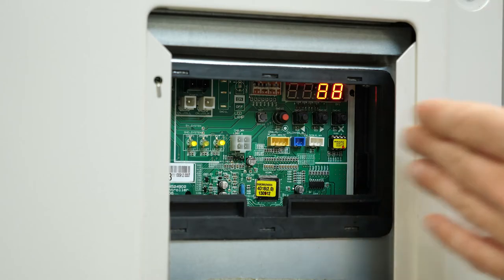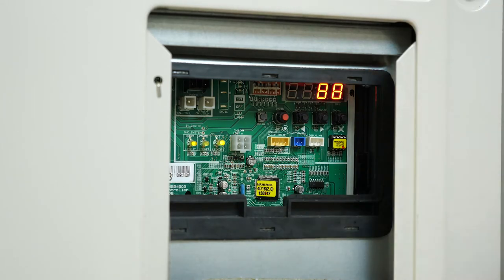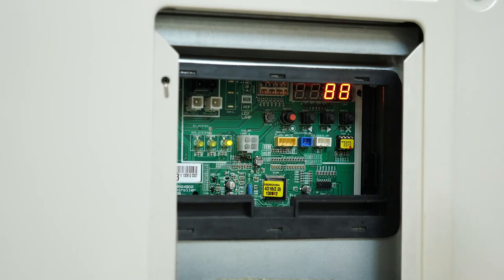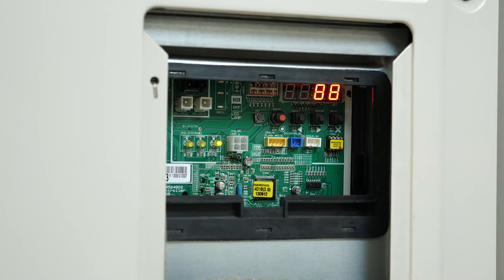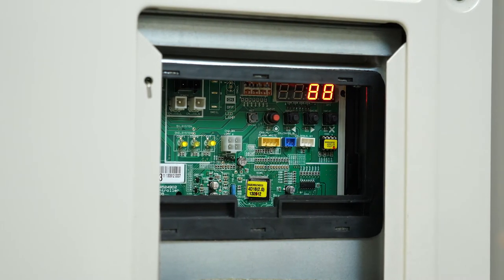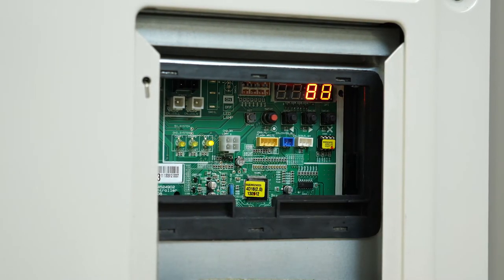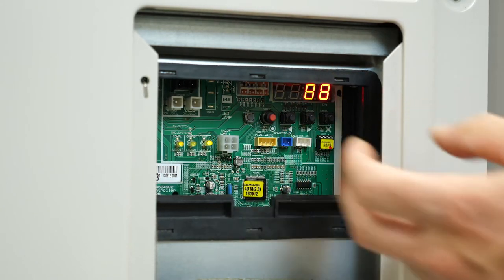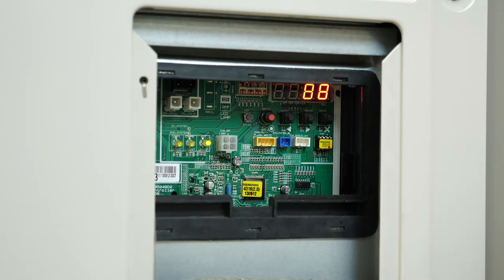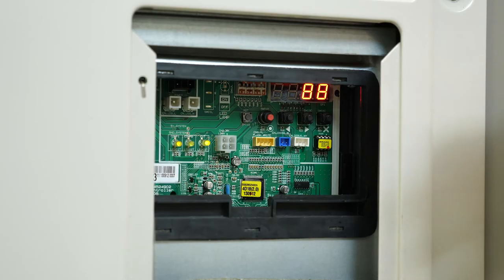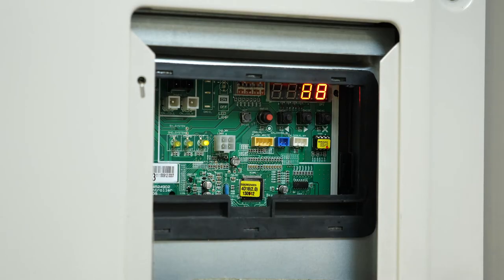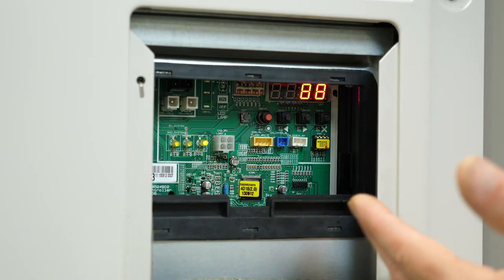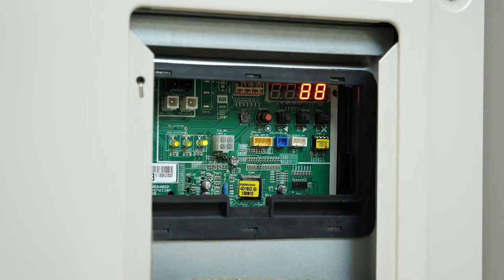On a heat recovery system, this would be your last resort for troubleshooting a communication error. On a heat pump system, because there is no auto pipe detect, we can just press that red button. It'll reach out to the indoor units, find that information, and bring it back in. Now we're just waiting for this heat recovery system to establish communication.